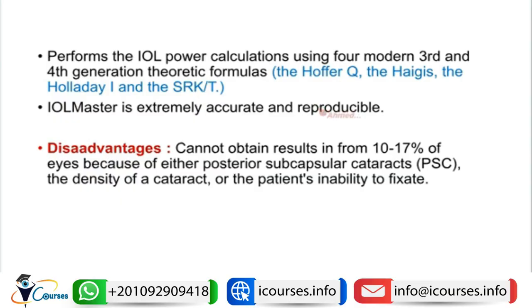The only drawback of this device is that, as we mentioned, it uses infrared rays. So if the patient has an opaque medium, for example, if he has a dense posterior subcapsular cataract, or if they have a mature cataract, then the infrared rays will not be able to enter inside the eye, and then it will not be able to calculate the axial length of the eye. It can measure the other measurements, but it cannot predict what the axial length of the eye is.